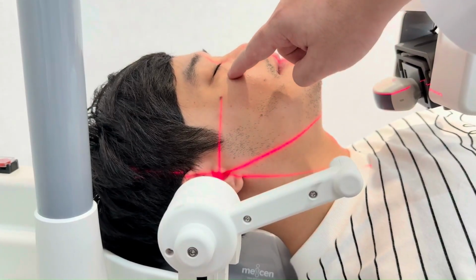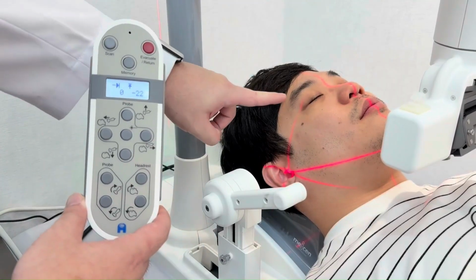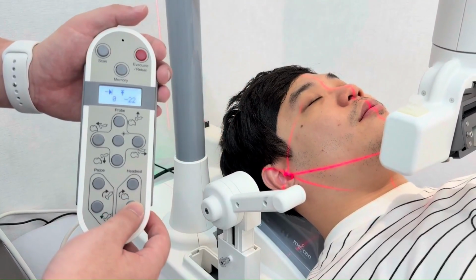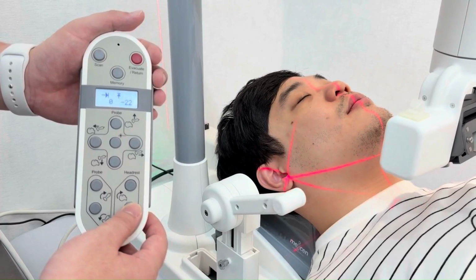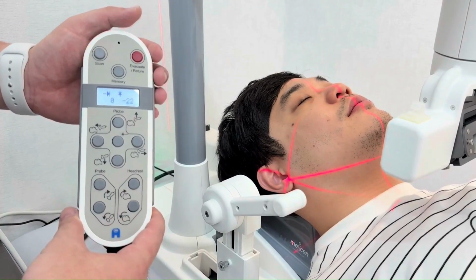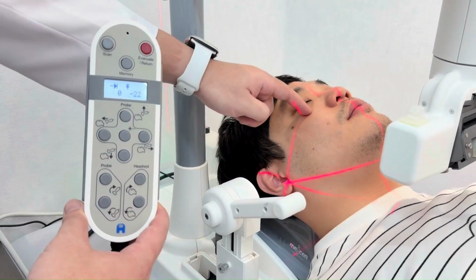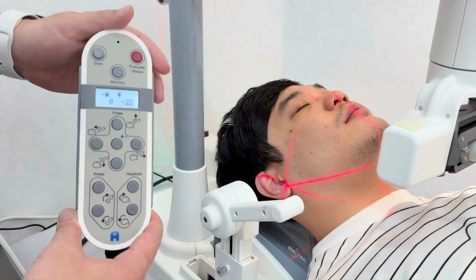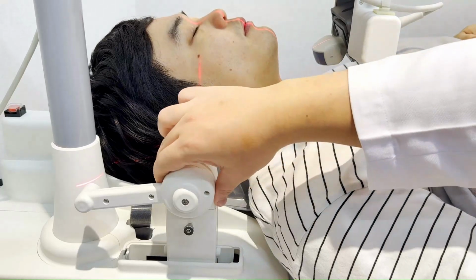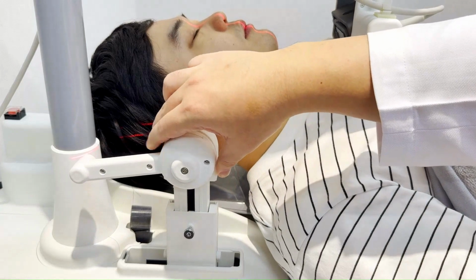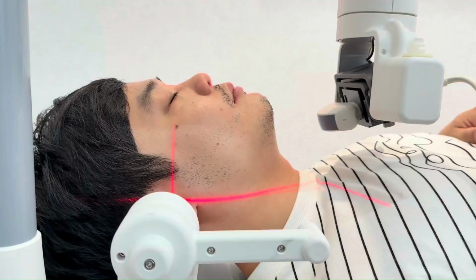Similarly, focus on the lower eye socket bone, not the eye itself. If the FH plane laser is misaligned, adjust the headrest height. Move the headrest forward or backward to achieve proper alignment between ear canal opening and lower orbital bone. If the laser module is not in the desired position, manually adjust it for proper alignment.